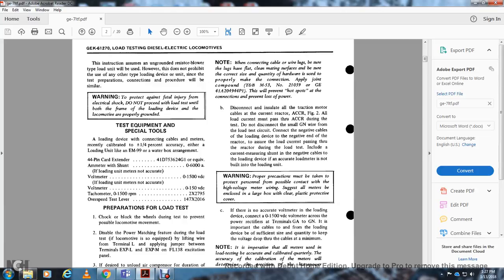B. Disconnect and insulate the traction motor cable to the current reactor for the ACCR, figure 2, for the load current path for the ACCR during the test. Do not disconnect the small GN wire for the load testing. Connect the negative cable of the loading device to the negative end of the reactor to show the loading current passing through the reactor during the load test.